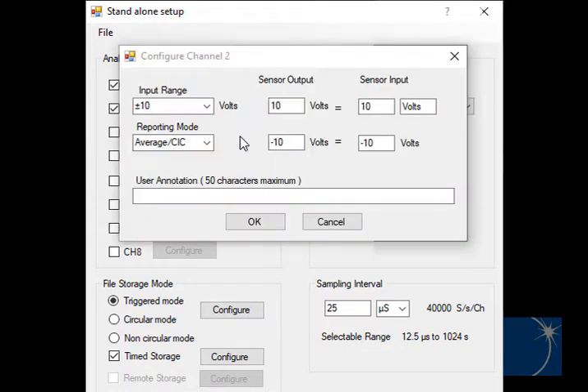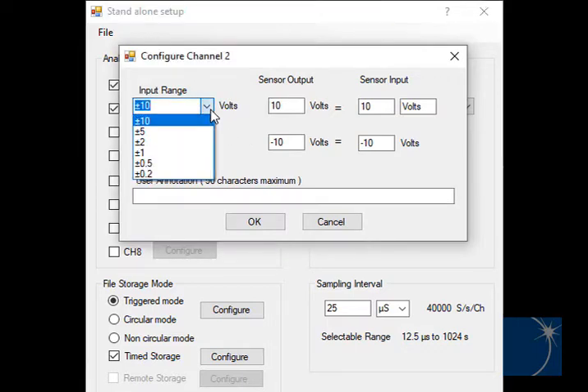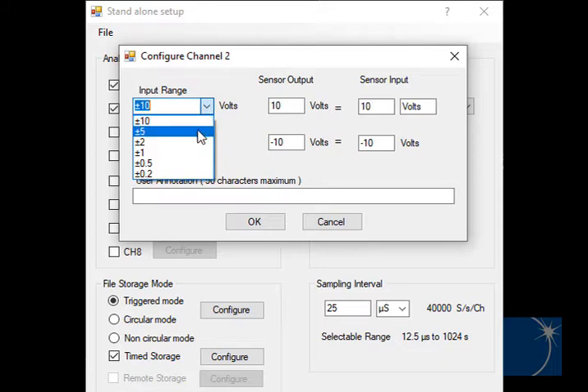In the Channel Configuration window, you can choose an input range. Note that the resolution of the instrument is spread out over the chosen range, so you want to choose a range that's wide enough to accommodate the signals you're connecting to the instrument, but narrow enough to give you the best possible resolution.